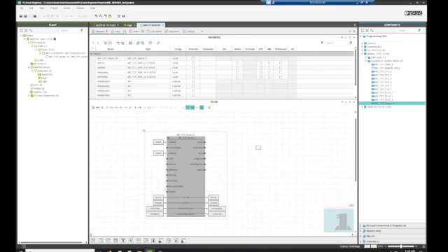And then the rest of these, we basically leave alone: whether you want to be in UDP or TCP mode, if we want to bind any of the IP addresses or ports so it can only talk to one specific device, we can do that. And then we have our reconnect delay and our timeouts. Those have some stock values in them that work for us, so we're just going to leave them alone. The last little bit is your ins and outs. So you're going to have your arrays of booleans with your array of coils and your array of inputs. And then you're going to have your array of words, which is your input registers and your holding registers.